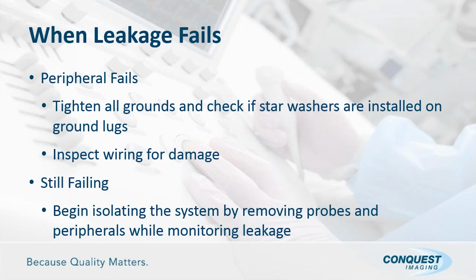After all of that, if you're still failing electrical safety, you're going to have to start isolating the different portions of the ultrasound system. Remove one probe at a time. Remove the peripherals so that they're not part of the circuit. As you're doing that, remove them one at a time and see which condition, if any, puts you back in an electrically safe condition. So you do them one at a time to try to figure out which device is causing it, and then go back and check that device.